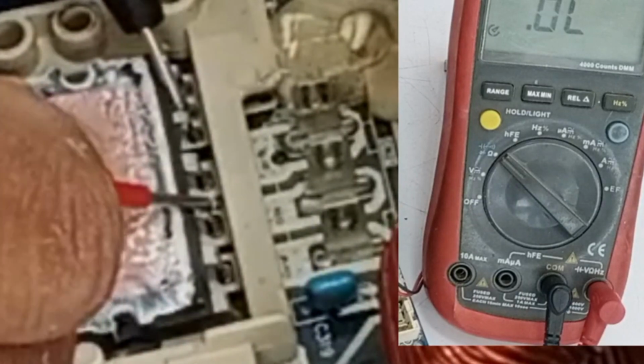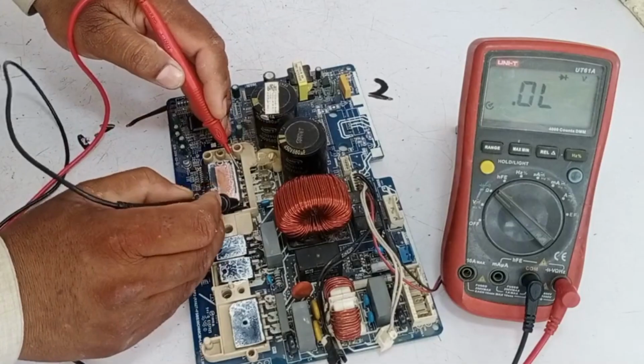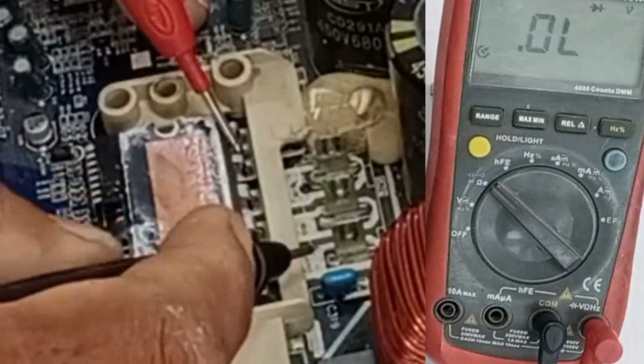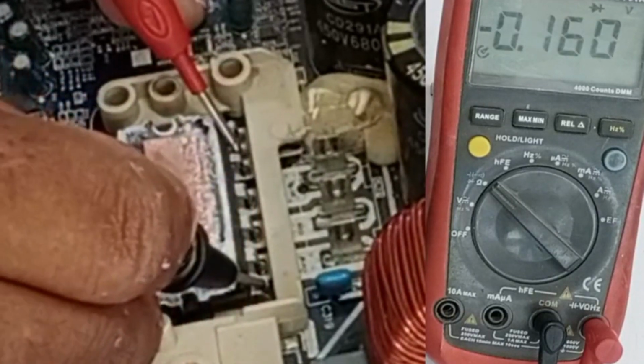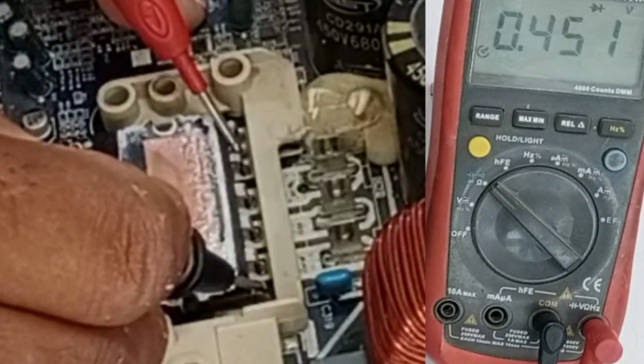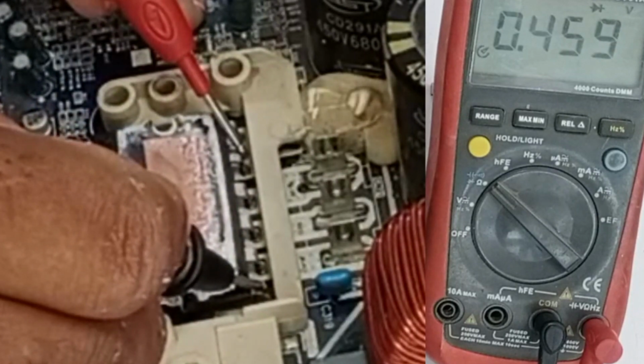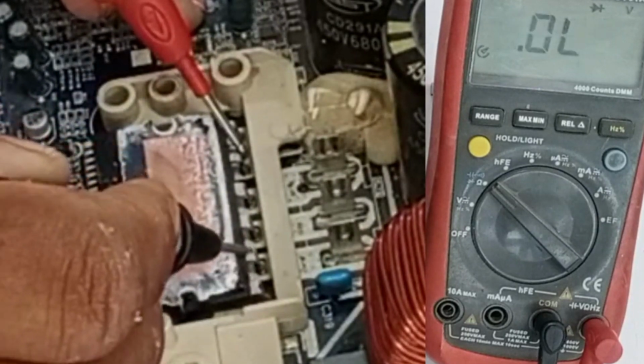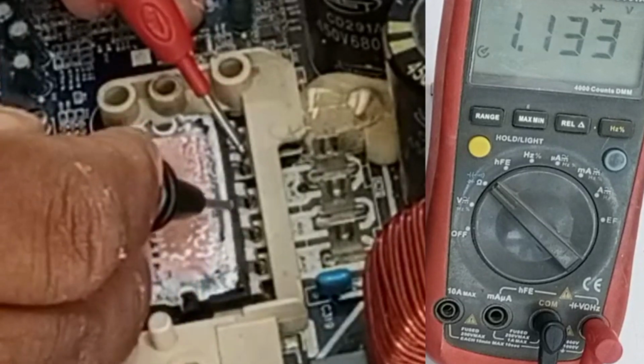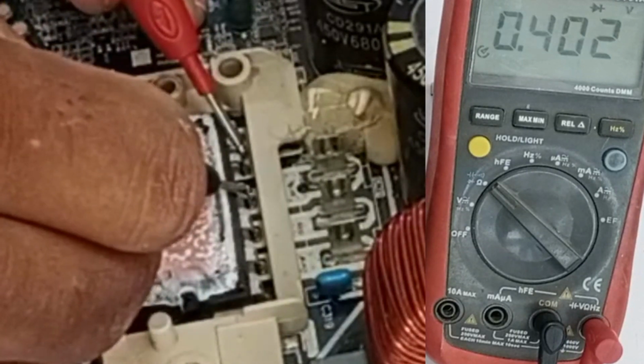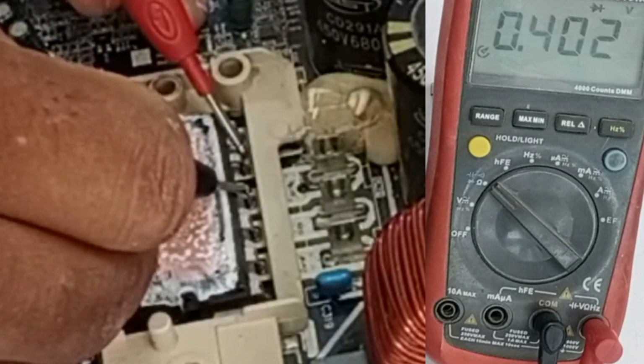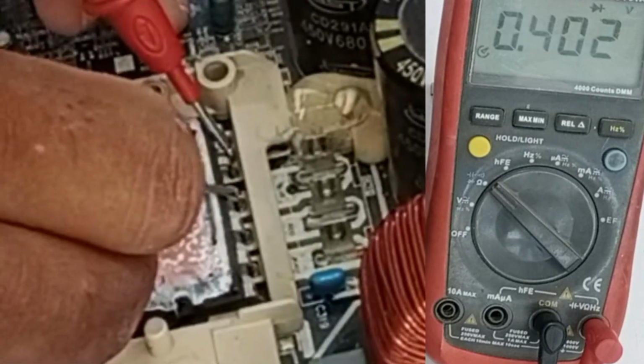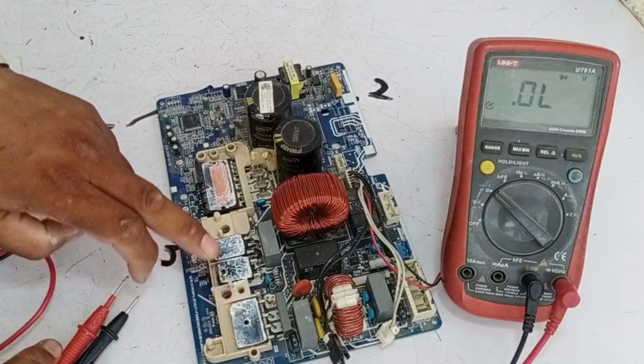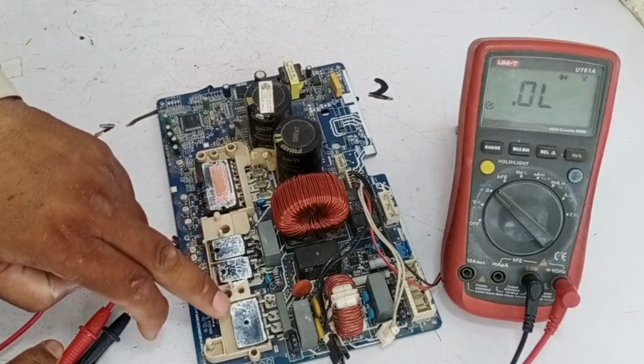There should be no value displayed, and as you can see, no value is showing on any point. Now, we will reverse the polarity of the probes. At this point, we should see some value, which will appear in the form of voltage drop. Here, it's showing 0.451 volts, so we should continue to see a similar value going forward. If any point shows 0, it means the IPM is faulty, and in that case, you would need to replace the IPM. So, all the points on the high side are perfectly fine, and there are no faults in them.